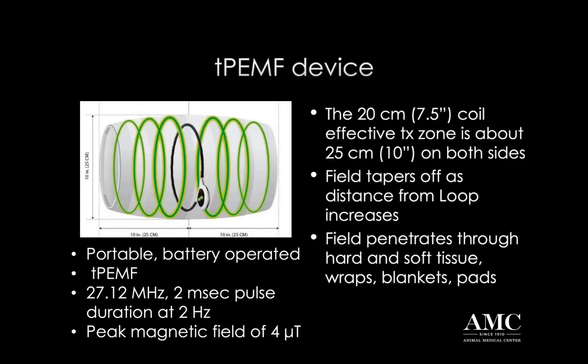The device delivers what we talked about - that 27.12 megahertz, which is FDA approved, with a two-millisecond pulse duration at two-hertz pulse frequency, with a peak magnetic field of four micro Tesla. We used to think it was only a field about two-thirds of the diameter of the opening, but we now understand it's actually much broader than that. It's going to go on either end of the opening of the Assisi loop to approximately 20 centimeters on either side. The field does taper off as you get further away from the target, but it will penetrate through hard and soft tissue - it'll penetrate through bone, muscle, and also blankets or bandage material.